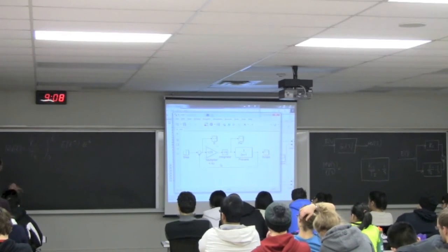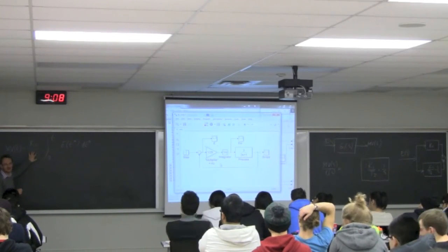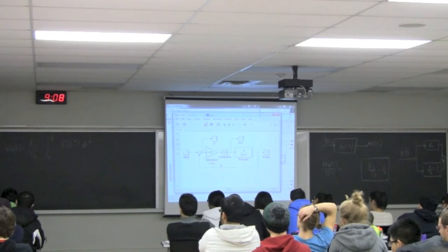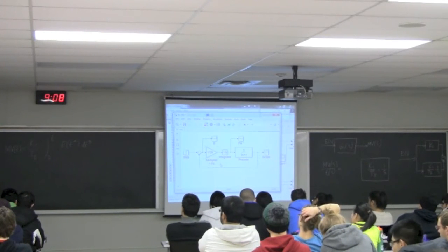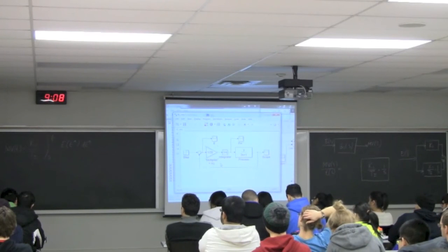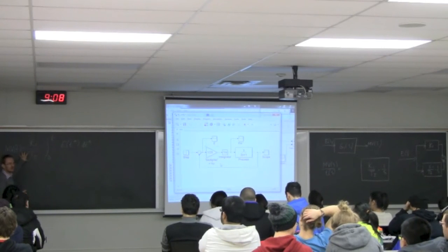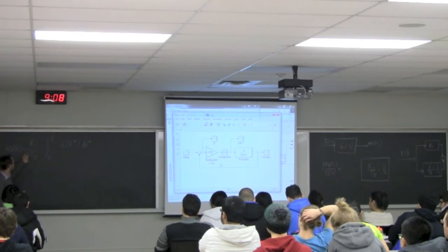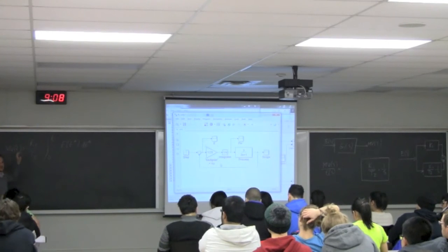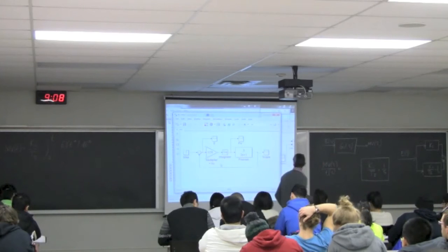Okay? So if I decrease TI, we've got 20 at the moment here. So if I make TI smaller, let's say I go to 5, what's going to happen to the manipulated variable? It's going to reach that point quicker. In other words, it's going to integrate this error, and whatever that area under the curve is, currently it's dividing it by 20. What it's going to do now instead is divide it by 5. So manipulated variable is going to be larger. It's going to take a more drastic or aggressive action.